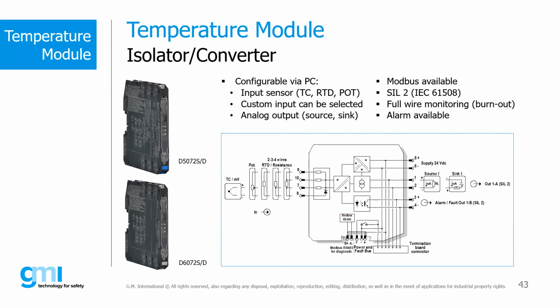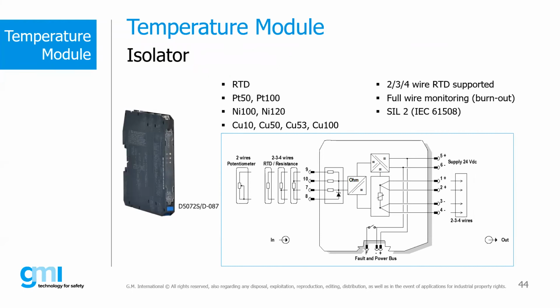And this is the purpose of these units, which can convert temperature signals with different standards, from RTD or thermocouples to 4-20. The output can be source or sink, with fault out, Modbus out, and so on. We also have a similar unit used as an isolator. In this case, we are repeating the standard from the field, from PT100 to PT100. This is used when the system card is able to read a PT100 or thermocouple directly. But of course, the application is for IS, so in this case a barrier or a certified isolator must be used.